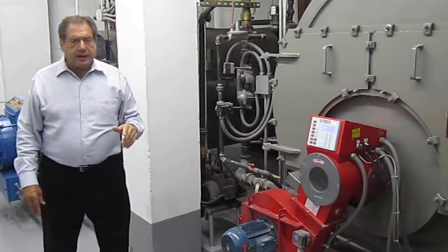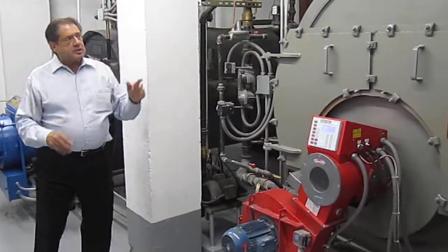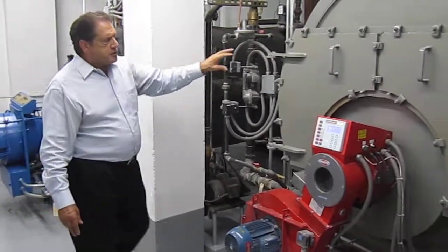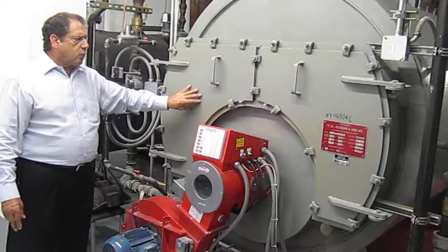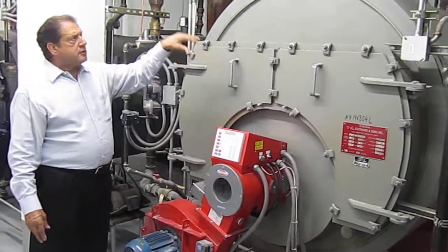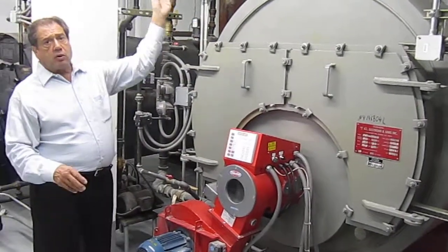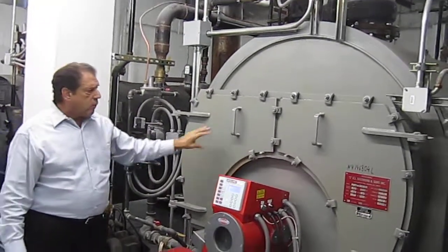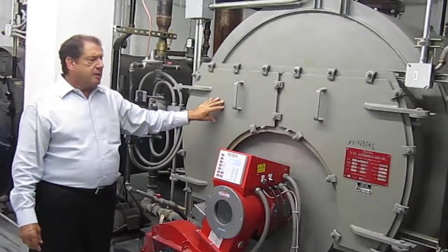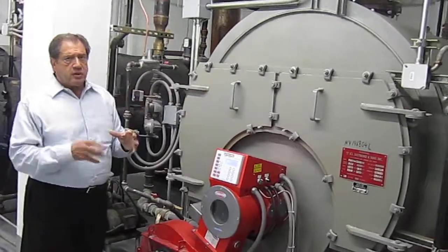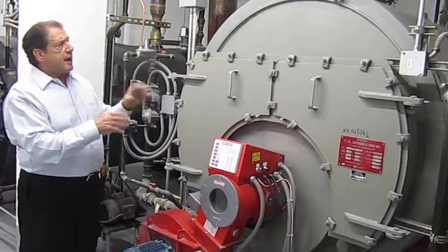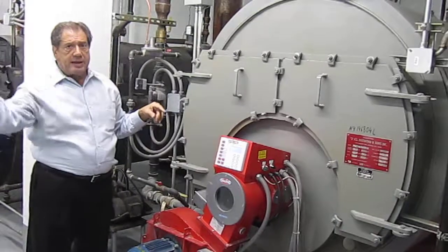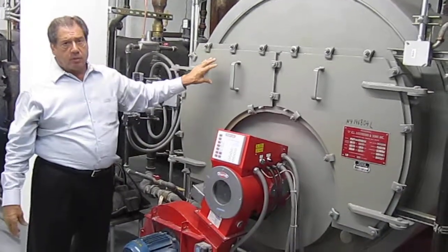The other thing I'd like to point out is the difference between a steam system and a hot water system. Before we spoke about how the tubes get hot. When the tubes get hot, the water around the tubes evaporates into steam, and then it gets channeled up into all the apartments. Well, in a hot water system, it doesn't operate that way. The hot water does not evaporate into steam. The hot water itself gets to a certain temperature, and then a valve opens and allows that water to go into the system. From the system, it gets piped into all the radiators and circled back into the boiler.